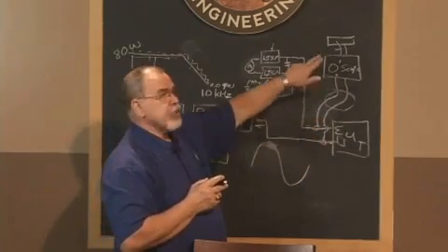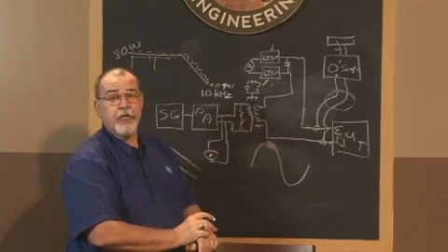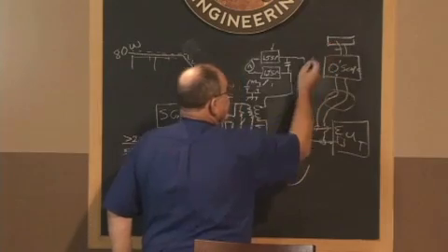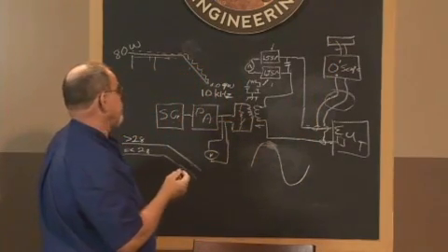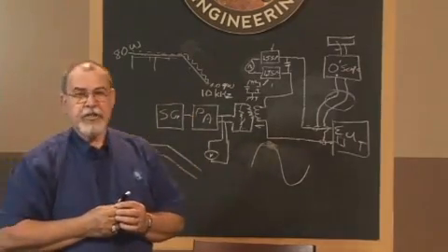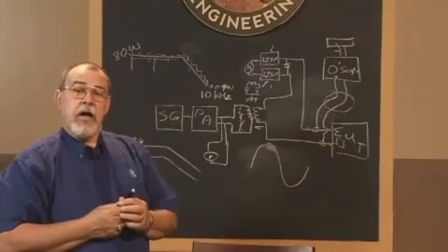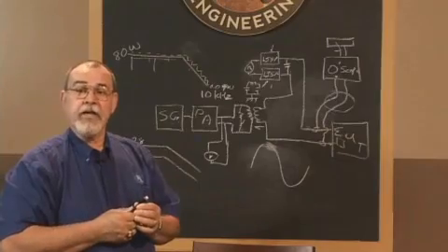So we always just isolate instead of being so sure about it. Okay? We don't want to provide another path for the currents. So typically we put an isolation transformer in place at the oscilloscope to prevent this damage. With that, that's a kind of coverage of CS101 and how we approach the test side of this. We can go to the laboratory and examine this, see what it looks like when we actually do the testing.